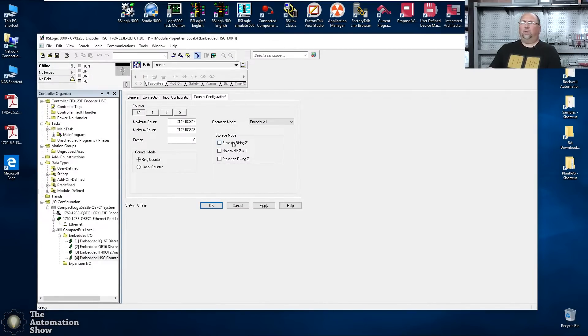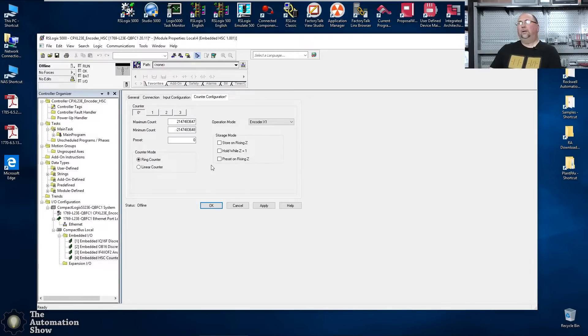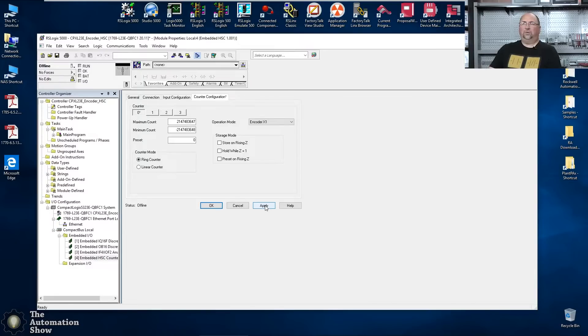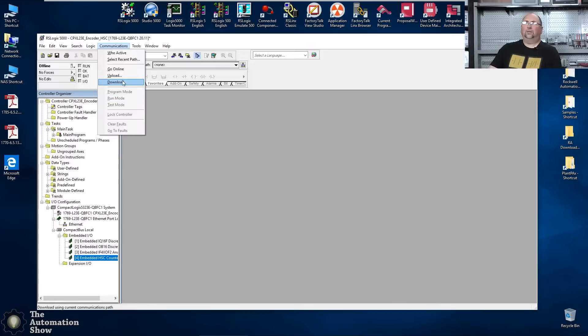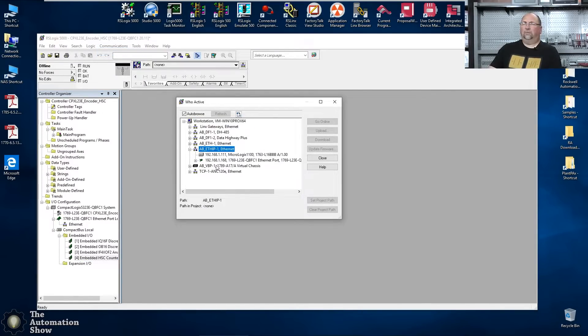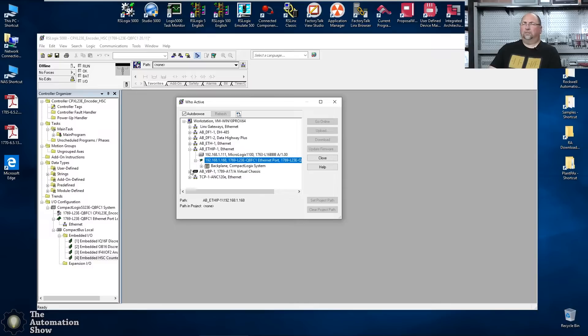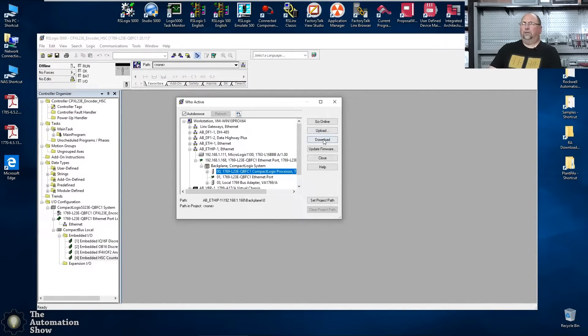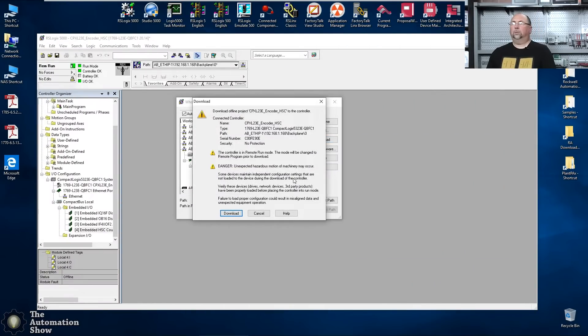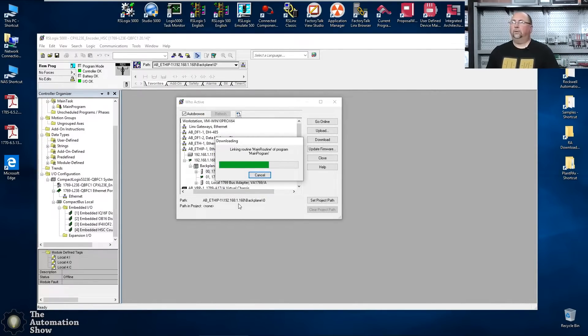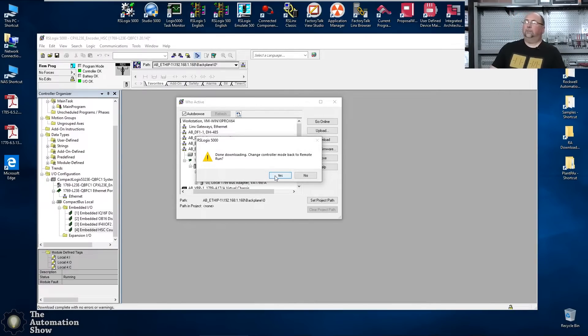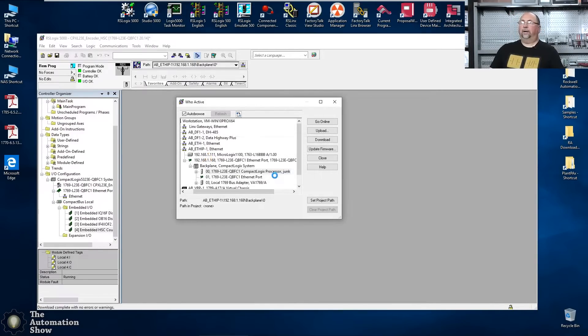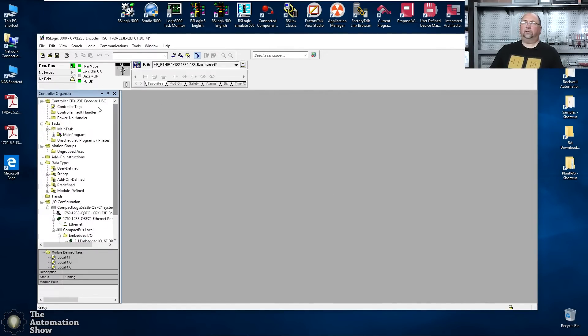We don't want to store or hold or preset on the rising Z. I am going to do a ring counter. I'm never going to get to the max, but if you do a ring counter, when you get to the max it will roll over. Is there anything else I have to do? This just seems too easy, doesn't it? Let's see here. Let me go to communications. Let's see if we can do a who active. Because this is an older unit, you actually have to browse through to the backplane to find the processor. And download. Since we're working on the bench, we don't have to worry about what happens in the field. And in mere moments, we will have downloaded. Let's put it back in run mode.